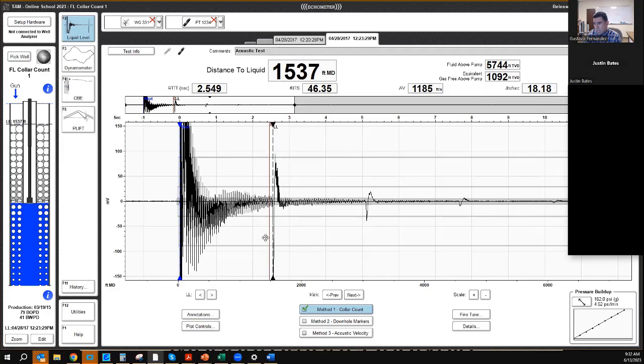We have a big down kick, and there's nothing that's supposed to create that but the liquid level, so I'm expecting to see a high liquid level. What this means is the liquid level line, the LL line, the time to that is RTTT, round trip travel time, appears at 2.5 seconds. So we have a down kick at 2.5 seconds, that's 2.55.